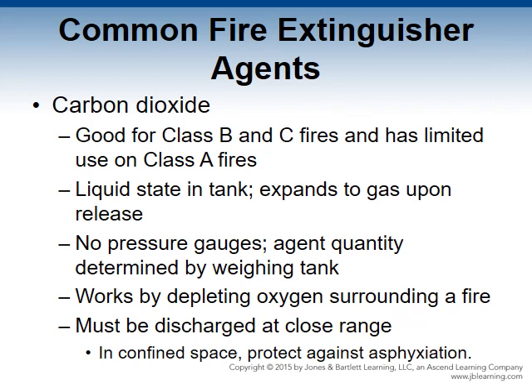Carbon dioxide is an effective agent for Class B and Class C fires with limited use on Class A fires. In the tank, carbon dioxide is in a high-pressure liquid state and expands to a gas upon release. The tank does not have pressure gauges; the quantity of agent is determined by the weight of the tank. These extinguishers are heavier than others of comparable size and rating. Carbon dioxide depletes the oxygen surrounding a fire and to a limited degree cools the fuel source. The agent must be discharged at close range so air movement does not carry the gas away. In a confined space, the operator must have an oxygen supply available to avoid asphyxiation.